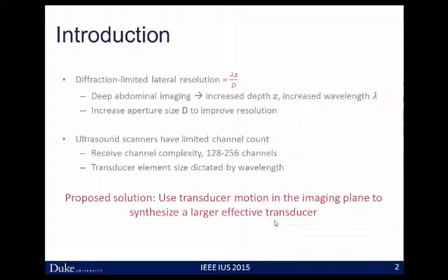In ultrasound, our lateral resolution is diffraction limited, and the focal spot size is given by the expression lambda z over d. When we do deep abdominal imaging, we're trying to image targets at a large distance z and at a long wavelength lambda, trying to achieve enough penetration at depth. The combination of these two factors gives us poor lateral resolution, often on the order of several millimeters.